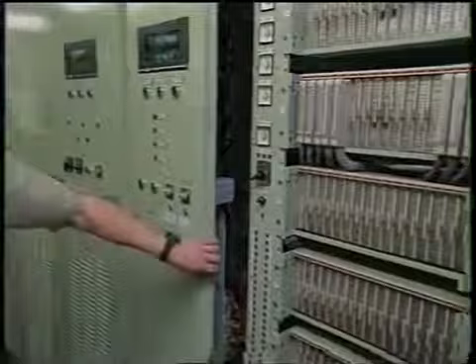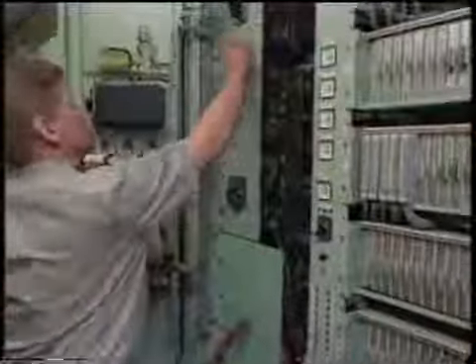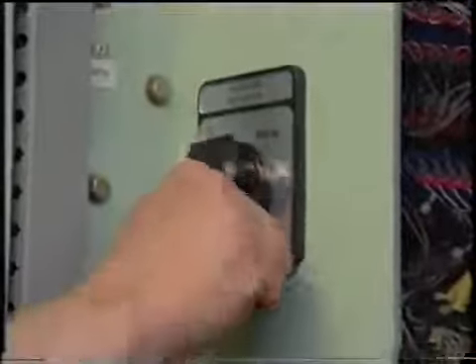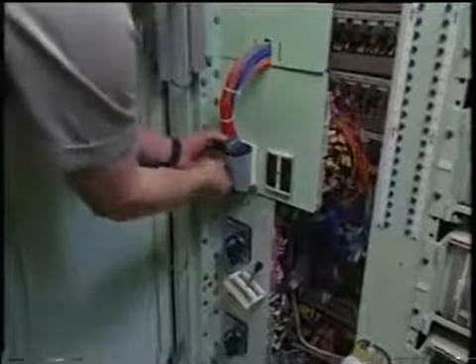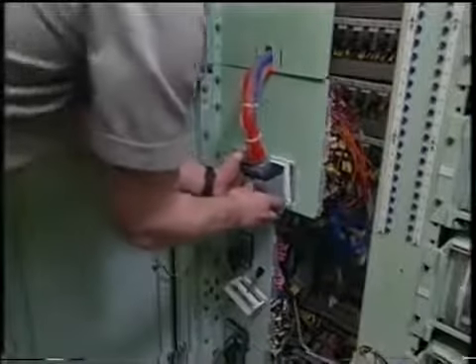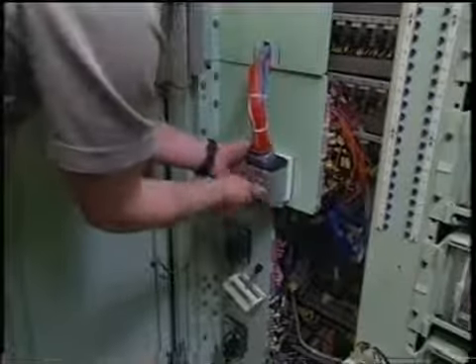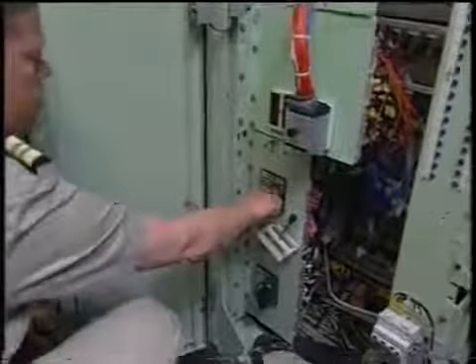Computers control the converters. There is one computer per propulsion motor. To ensure smooth running and to have built-in redundancy, there will be 3 computers available. The third computer is online and tracks normal operations, but to ensure that it will cope with handling the propulsion on load, it will be regularly switched into service. To achieve this, the power supply to the propulsion motor has to be switched off before the changeover of the computers.